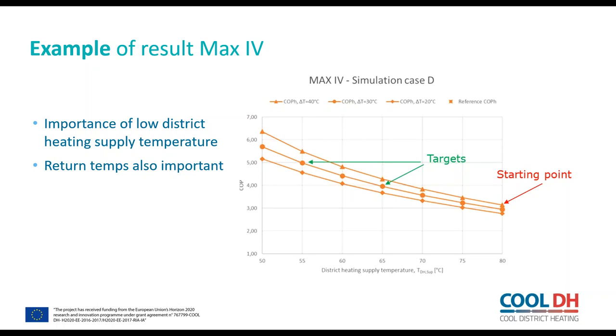So, well, the supply temperature has a large impact on the COP. And also the return temperature, you see the three parallel lines, they are the different temperature differences. So at a temperature difference of 40 degrees, you get a much higher COP than a temperature difference of 20 degrees.